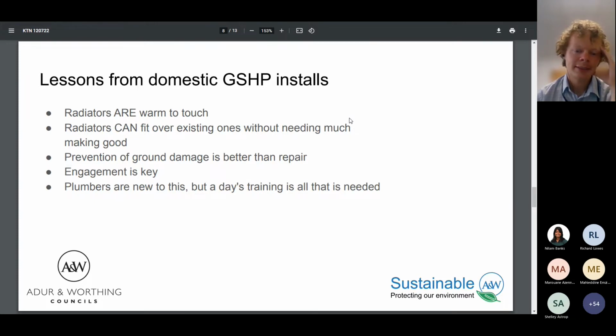Finally, it's often said that industry isn't up to scratch at the moment. On one of the two sites, the subcontractor installing the plumbing works had never installed Kensa heat pumps before, in fact the team may well have not installed any heat pumps of this kind before. However, the plumbing was essentially identical, and all it required to upskill the entire team was a day's training on purging and commissioning the system. I would now not hesitate to use them on another heat pump project.